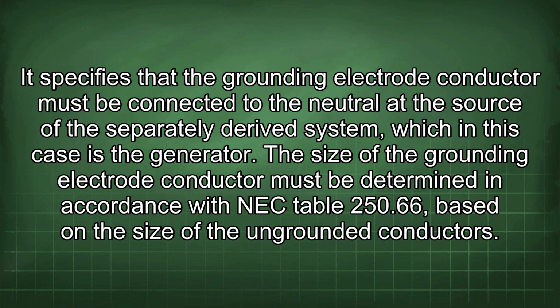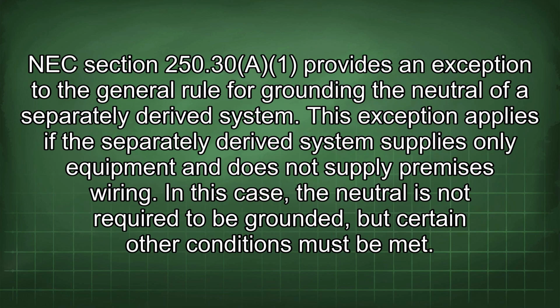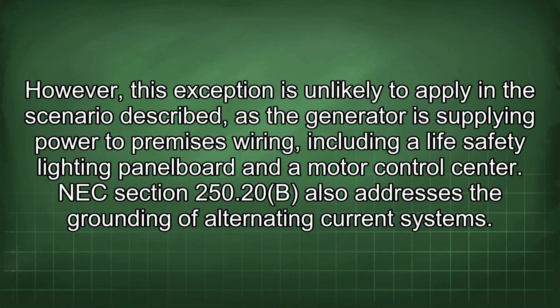The size of the grounding electrode conductor must be determined in accordance with NEC Table 250.66 based on the size of the ungrounded conductors. NEC Section 250.30 provides an exception to the general rule for grounding the neutral of a separately derived system. This exception applies if the separately derived system supplies only equipment and does not supply premises wiring. In this case, the neutral is not required to be grounded, but certain other conditions must be met. However, this exception is unlikely to apply in the scenario described, as the generator is supplying power to premises wiring, including a life safety lighting panel board and a motor control center.